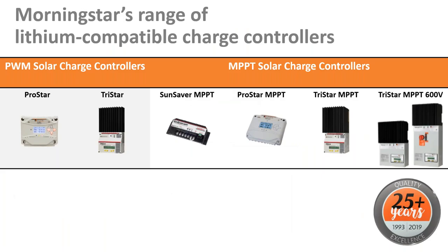Regarding lithium compatibility—which is why we're here today—many of our products also contain full programmability options. Those include the ProStar and TriStar, SunSaver MPPT, and ProStar MPPT. Both PWM and MPPT solar charge controllers have programming options allowing them to be custom configured for a variety of battery chemistries, and specifically for the needs of lithium with lithium-centric settings.